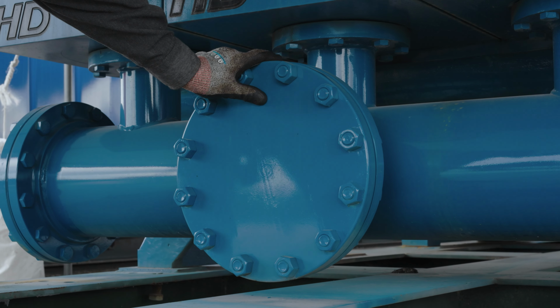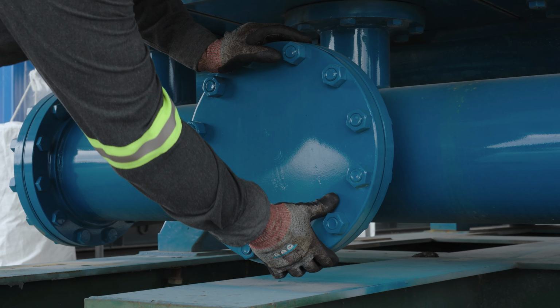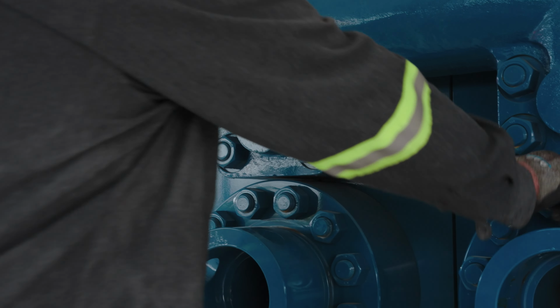Next, move down to your suction manifold. Check all your gaskets on your suction manifold. Make sure the gaskets are not leaking and that there are no loose nuts.